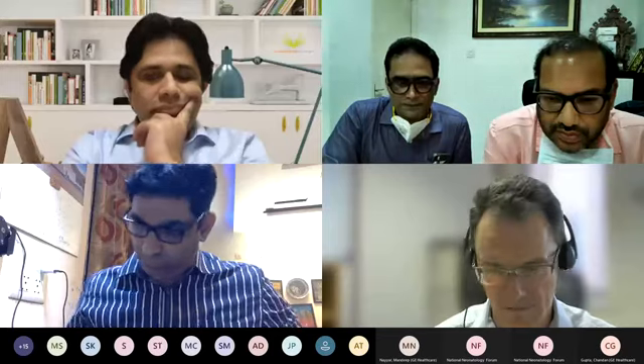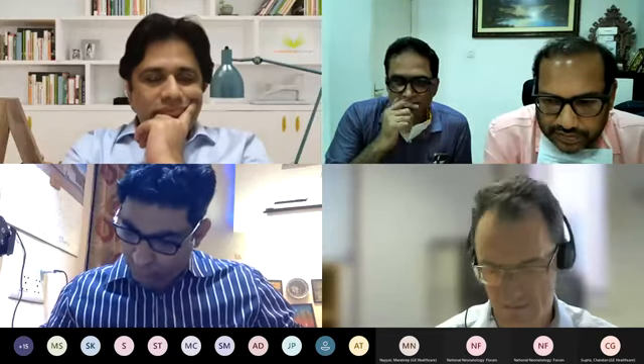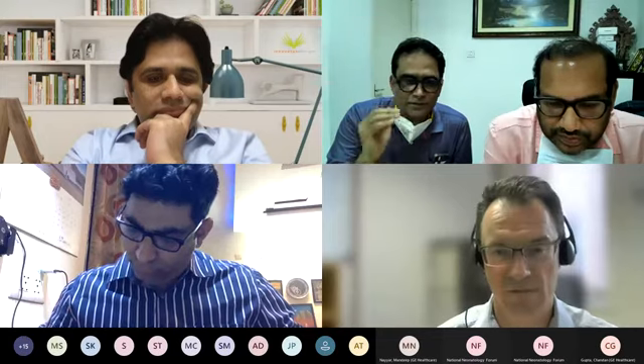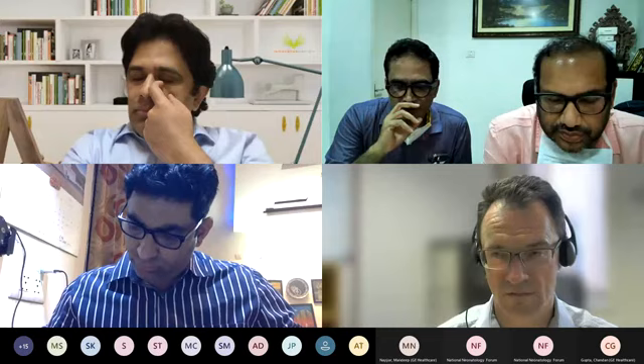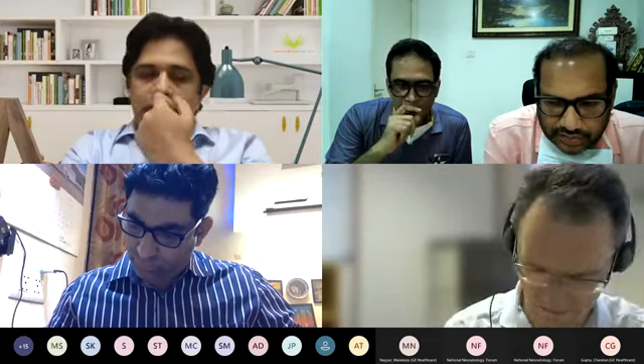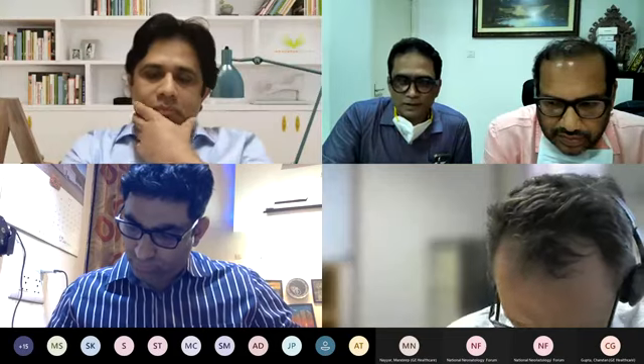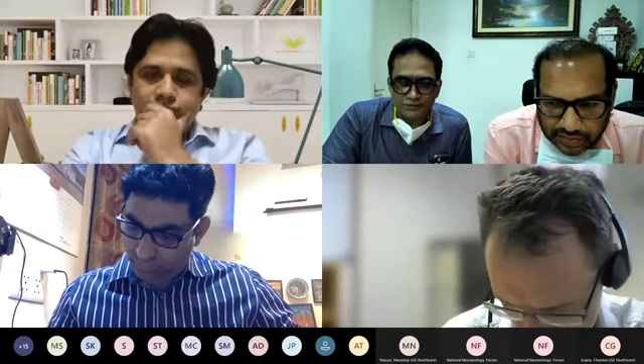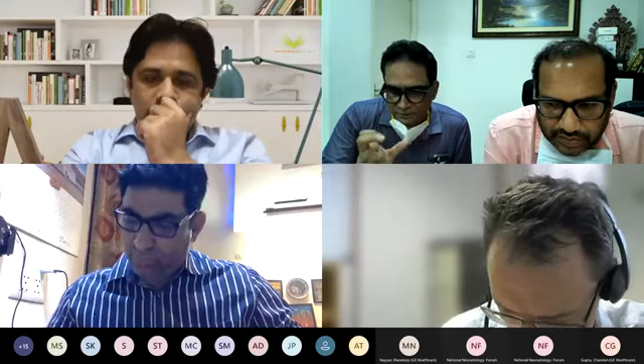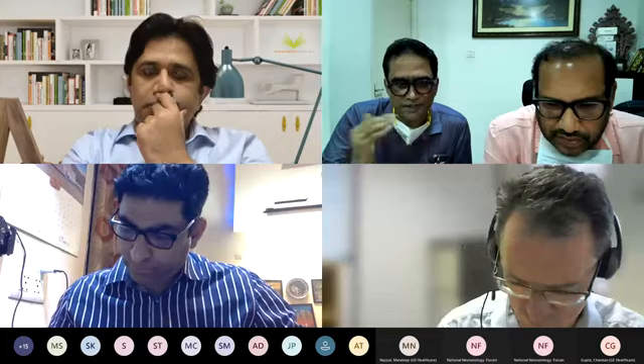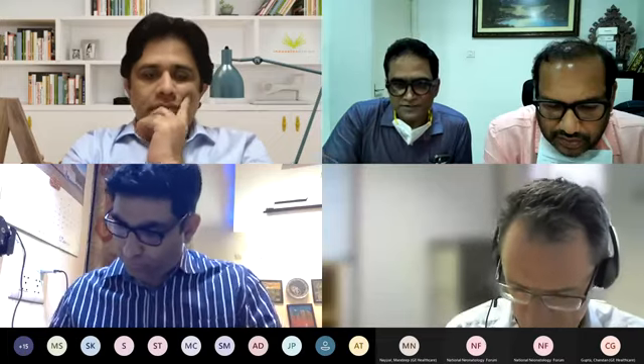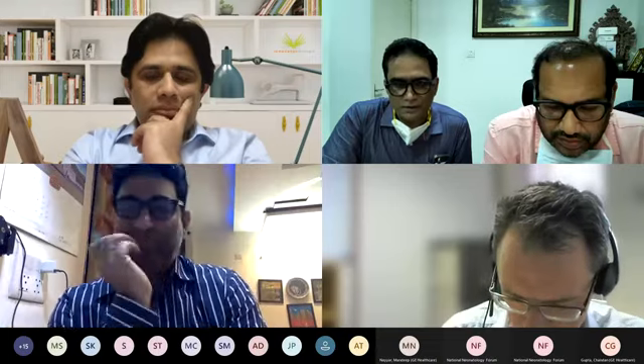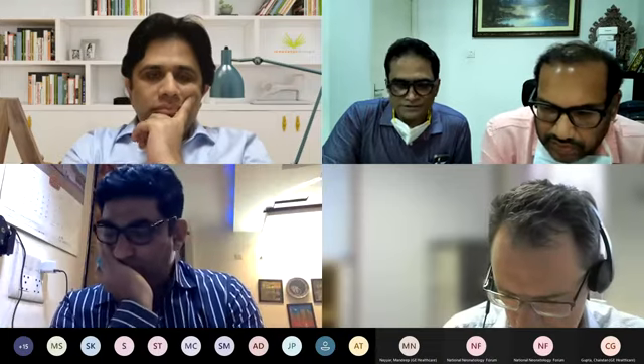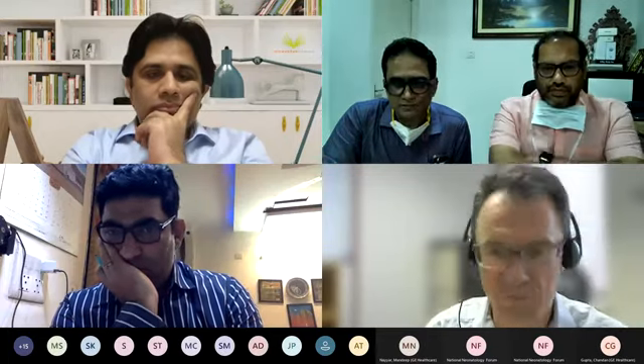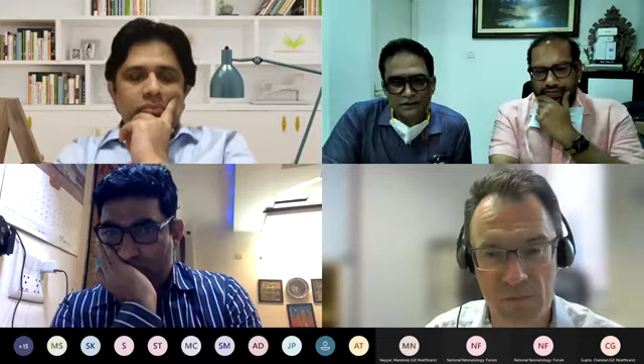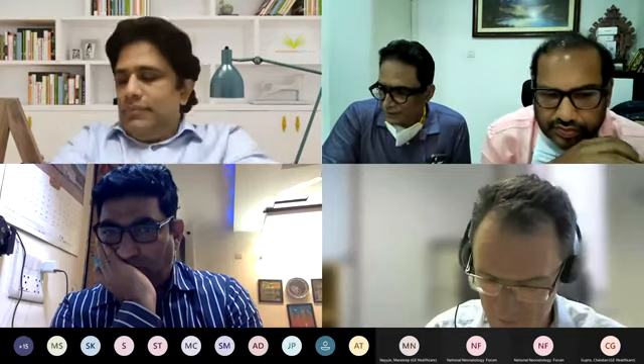Number two, sometimes, even though the flow sensor is calibrated and brand new, there is a discrepancy between the set tidal volume and the delivered tidal volume. Even though the baby's lung compliance is good with adequate peak inspiratory pressure, there is some discrepancy which we had to overcome by adjusting a few things. We have the latest software update on that, but there are still fine tuning issues that I have noticed. I just wonder what your thoughts are.